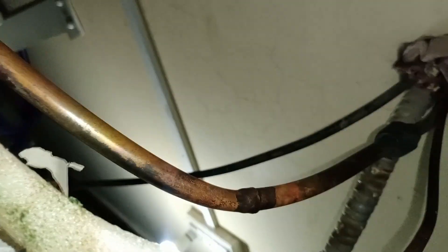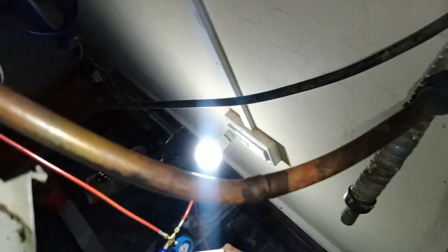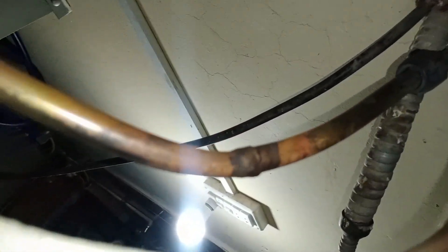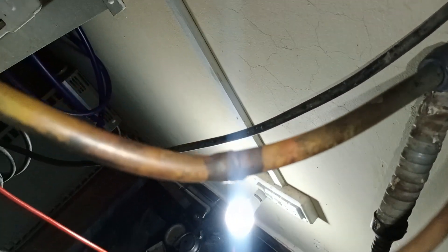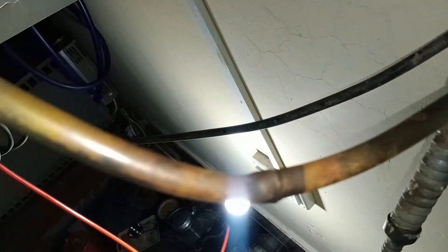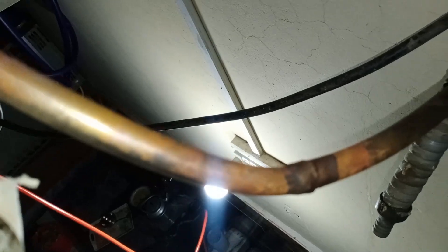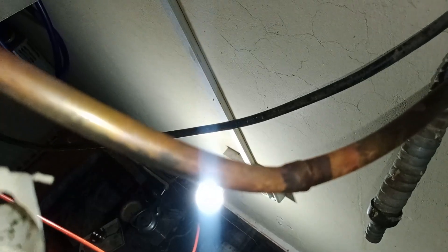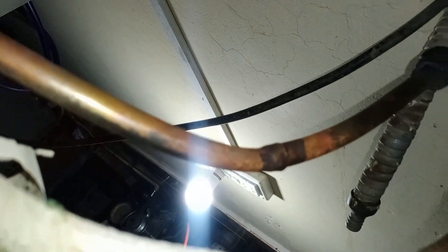After installing the new joints and fixing the pipe, the unit was tested and it started working perfectly. The ice formation issue was completely resolved as well. This highlights the importance of inspecting the entire system, including the outdoor unit, for physical issues like bent pipes that can restrict gas flow and cause such problems.